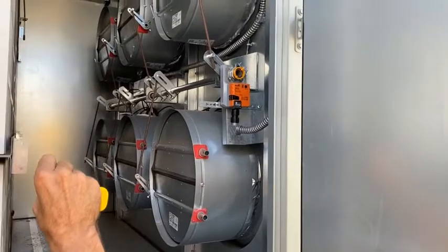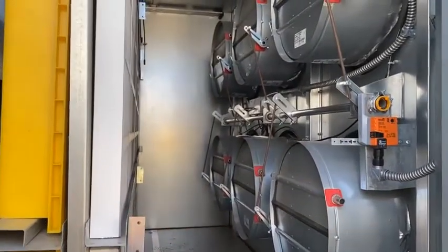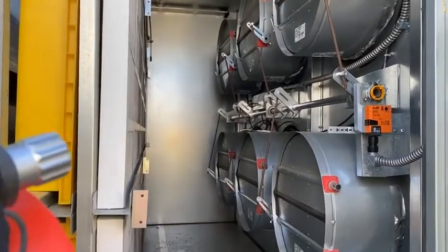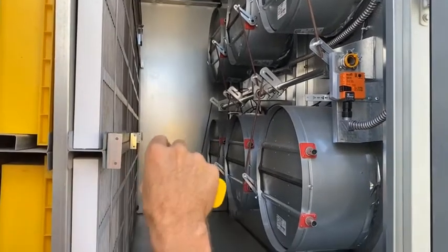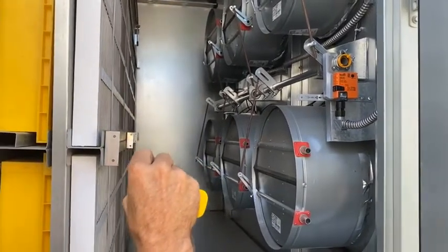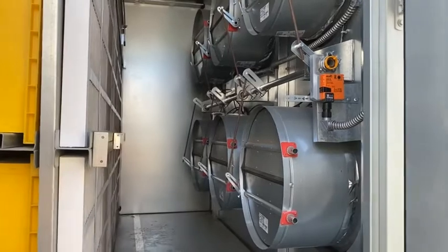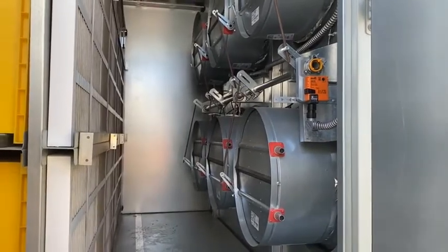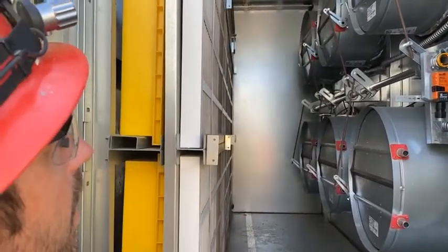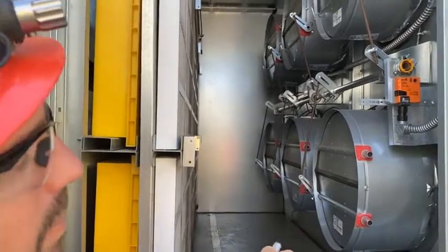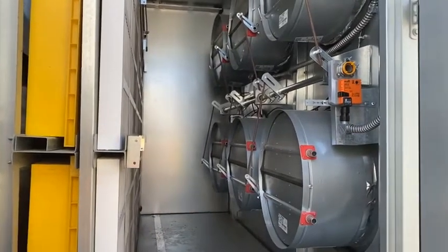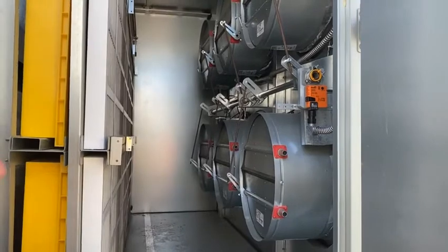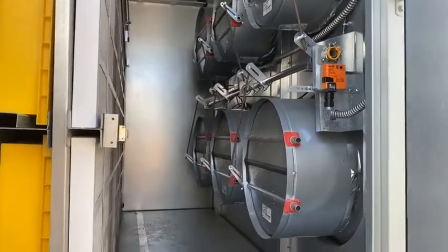And it was set by the balance guys. Yeah. So this box right here is holding the computer board that's taking the data from each one of these ports and then adding up that CFM, giving a total right here, and the BMS guys are picking up that point, okay? Then they open according to the need? They'll modulate this damper depending upon the outside air economizer, or no, this actually should stay open all the time. This is a 100% outside air unit, okay? There's no return air on this.